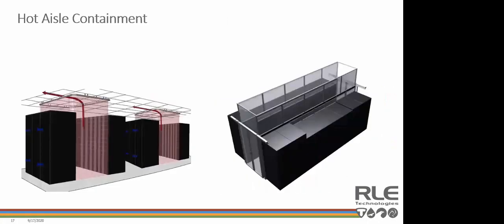So here are some examples of soft and rigid hot aisle containment solutions. The image on the left shows a soft curtain hot aisle containment. Although hot aisle containment can be done as a retrofit to an existing space, we see it installed most often in data centers that are purpose-built for it. The image on the right also shows a hot aisle containment solution, but it's made using rigid panels. Doors on the ends of the aisles allow access to the backs of the server racks. While rigid containment can reduce leakage and lead to a more efficient cooling system, it's also more expensive. As mentioned with hot aisle containment, retrofitting a space to include a ceiling return air plenum can be costly and typically requires additional fire suppression systems for the ceiling plenum.